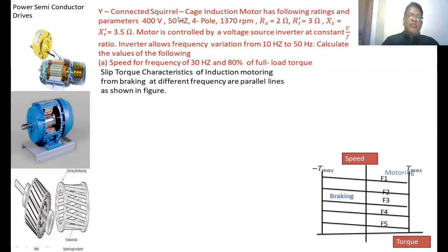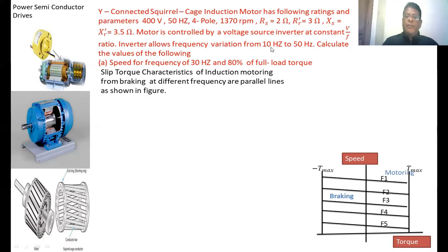Now we look at the second problem: a star-connected induction motor with the following rated parameters — 400V, 50Hz, 1370 RPM. Stator resistance RS = 2 Ohm, rotor resistance referred to stator RR' = 3 Ohm, stator and rotor leakage reactances XS = XR' = 3.5 Ohm. The motor is controlled by a voltage source inverter at a constant V/f ratio. The inverter allows frequency variation from 10 Hz to 50 Hz.